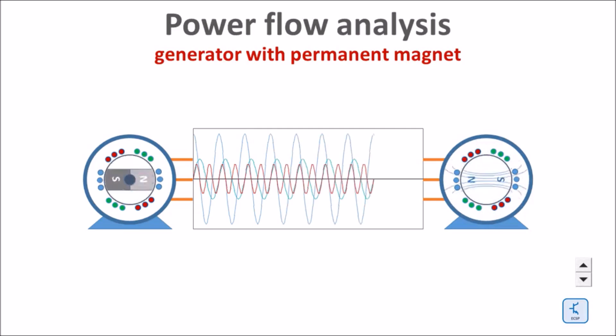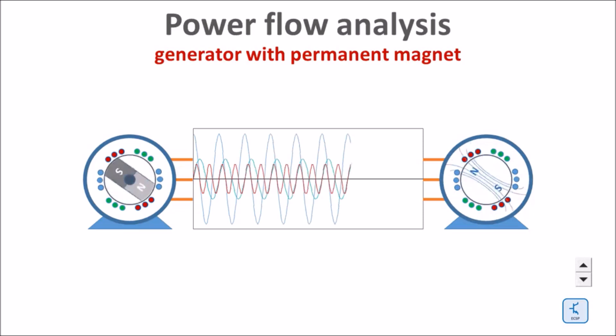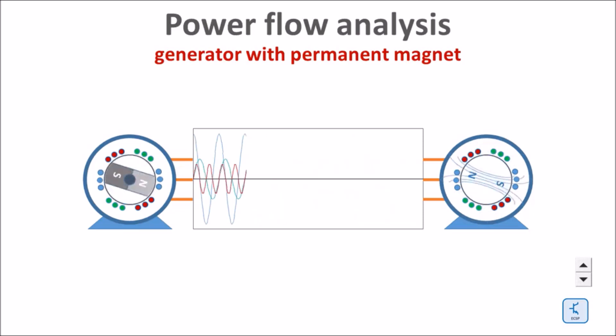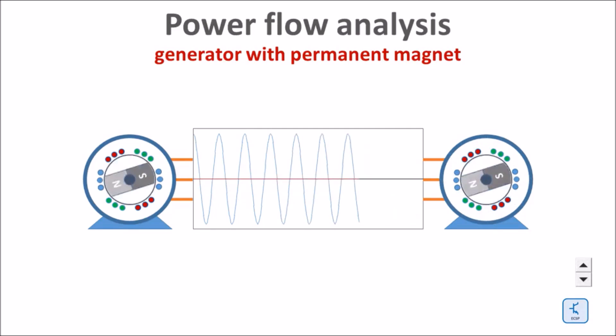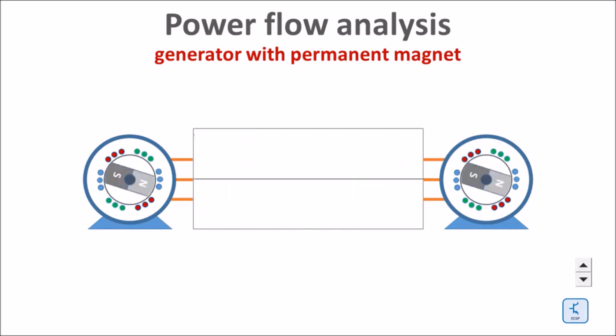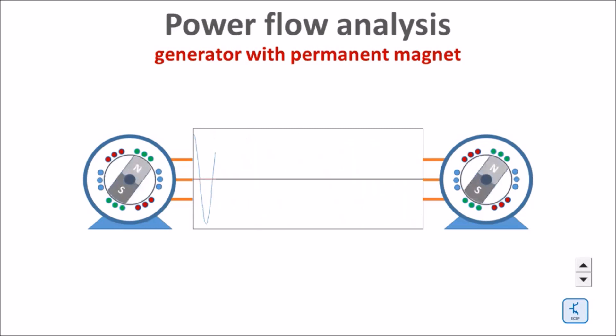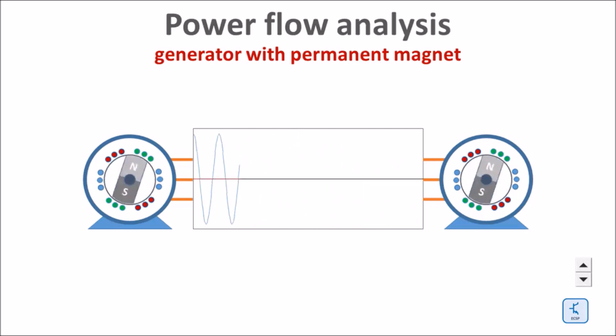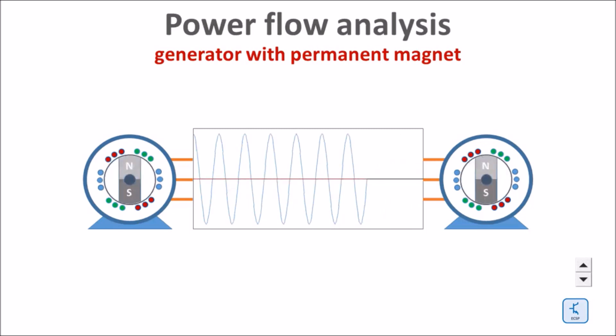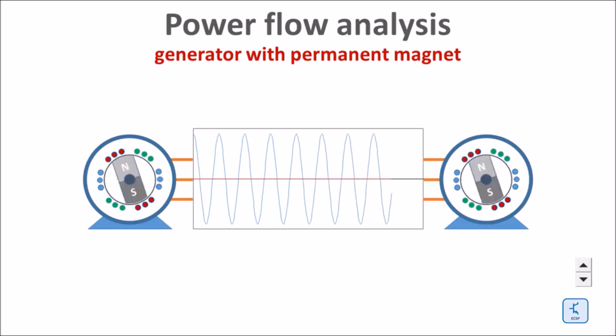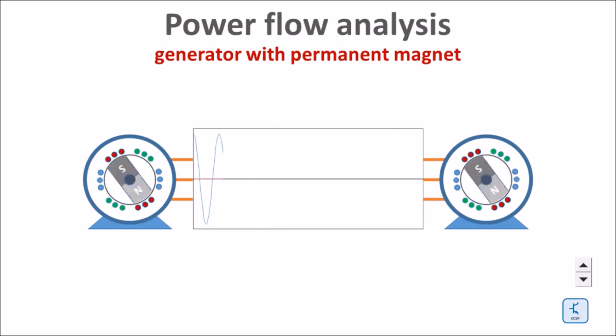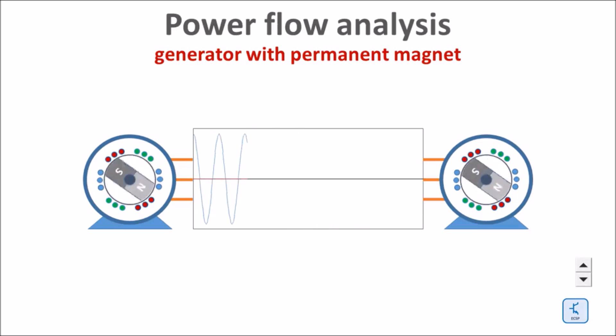The red curve shows that there is reactive power flowing from generator A to generator B. For simplification reasons here I show only one of the three phases. At the very moment when both generators are equipped with the same magnetic rotor and both rotors rotating perfectly in sync, no phase angle between them, the generators are perfectly balanced. Both produce the exact same phase voltages. There is no current flowing between them and thus no reactive or active power exchange.